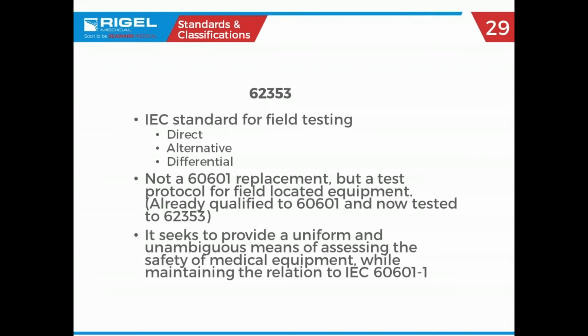Under the 62353 test standard, we said it's a little kinder, easier on a piece of equipment. But there are three different ways in 62353 that you can test equipment: direct, alternative, or differential. Direct is simply what you would have done, a direct method of testing. Alternative says take your ground wire, if it's Class 1, take your lead wires, put a voltage on all those leads, and look at your leakage currents. So we're still dealing with either 250 or 500 volts. For now, it can be done at 50 volts DC, 100 volts DC, 250 volts DC, or 500 volts DC. So you can have that voltage put on it to do that test.